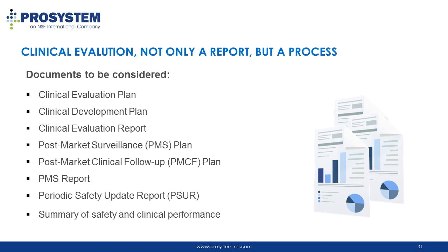Not long ago, the term clinical evaluation would be associated only with the preparation of a clinical evaluation report. However, we should keep in mind that the preparation of a clinical evaluation report involves a continuous process to acquire and evaluate clinical data. This data should then be documented not only in the clinical evaluation report, but also in a number of other documents, the requirement and update of which differ according to the medical device classes. In the next slides, I will go through the requirements for the preparation of these documents.